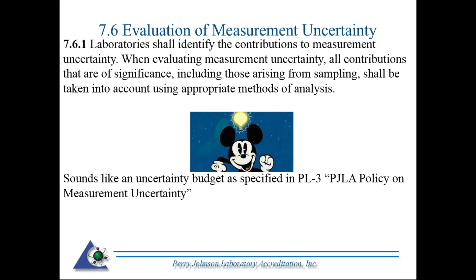For those of you that may not be that familiar with an uncertainty budget, here's an example one. As the requirement states, you're identifying the significant contributors. Here's an example of an uncertainty budget for a calibration of an infrared thermometer, one of those temperature devices that will shoot lasers and give you the temperature of where it is focused. So we're identifying the contributors. We typically have repeatability, uncertainty of standard, resolution of the device. Here we have other things that are pretty much specific to the type of calibration. Overall, we have 6 contributors identified here.